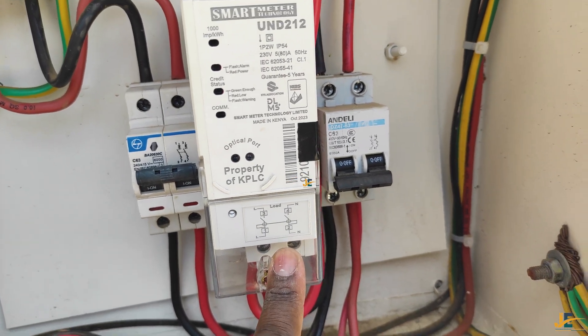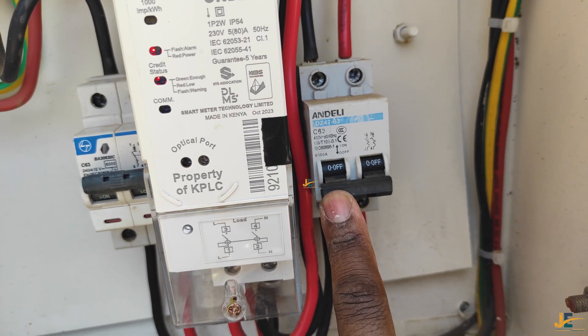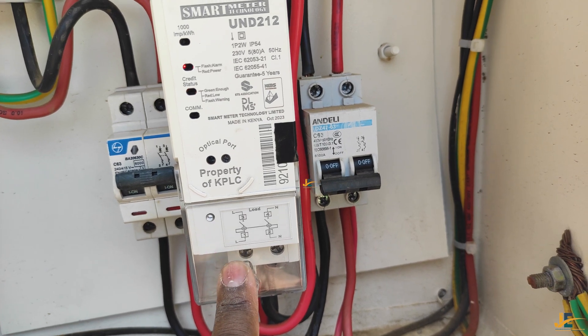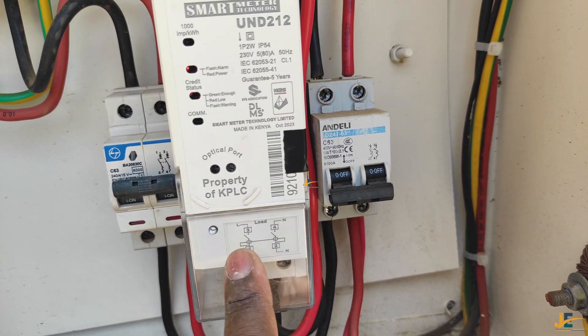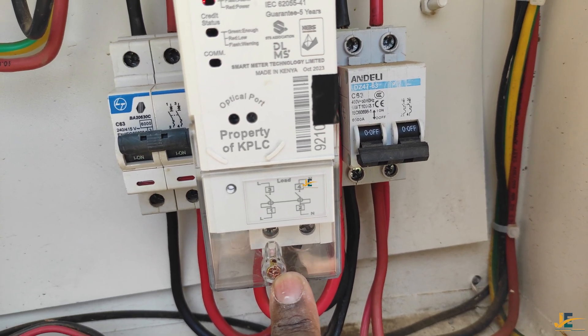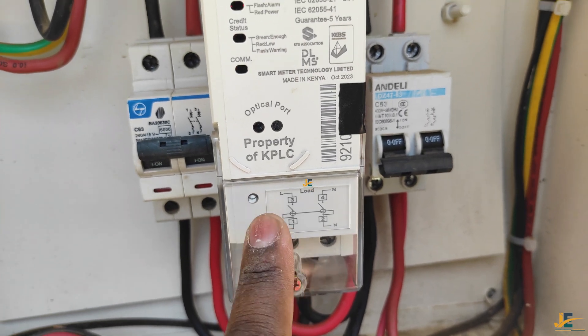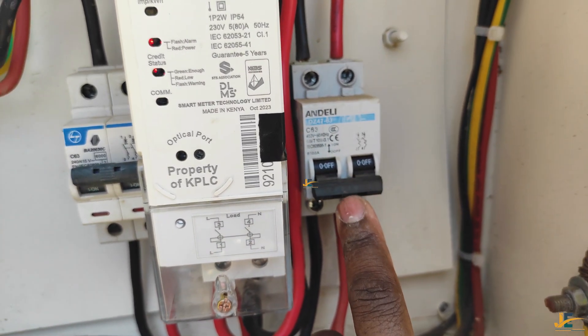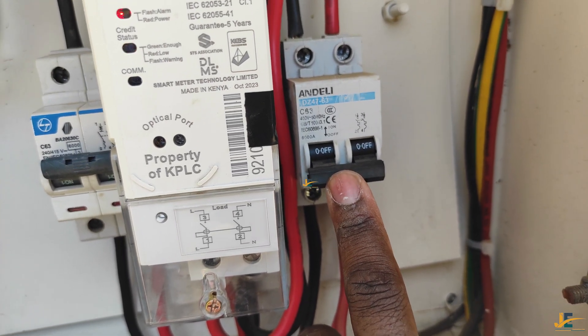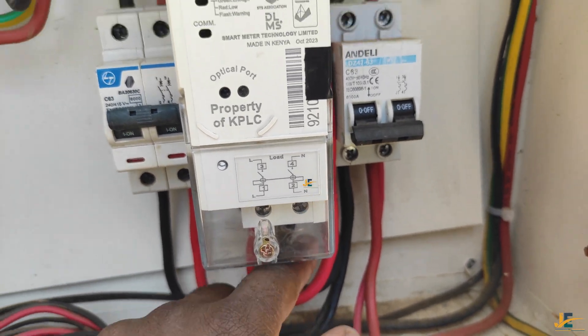To avoid tamper mode, you can also add another double pole. This is for future use — to avoid having to open the terminal cover in the future if you'd like to add another load. If you open this terminal cover, this meter will switch to tamper mode. So since you won't be able to open this meter, you are supposed to use another MCB double pole — a C63 — whereby the meter output feeds into this second double pole.